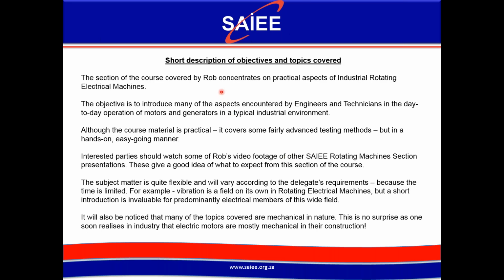Okay, my course is, when I looked at it, I'd say practical aspects of rotating machines. If you look at the content, you'll see it's all about getting the most out of your industrial machines, i.e. preventing failures, what you can do to prevent failures. So there's some design aspects. Mostly it's condition monitoring, testing, and then I look at two specific types of failures that occur on machines. It's very practical, but you'll see that we go into some fairly advanced testing methods like partial discharge, rotor flux, and even vibration can get very advanced for an electrical engineer or a practitioner in general. But it's in a hands-on, easygoing manner.